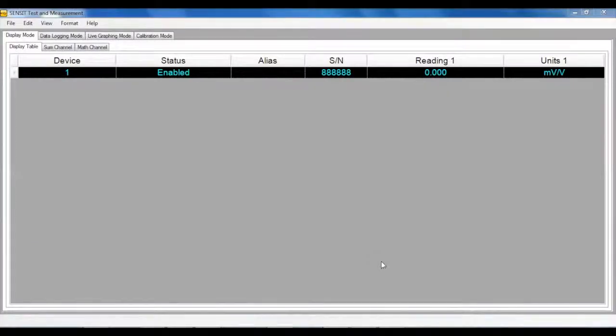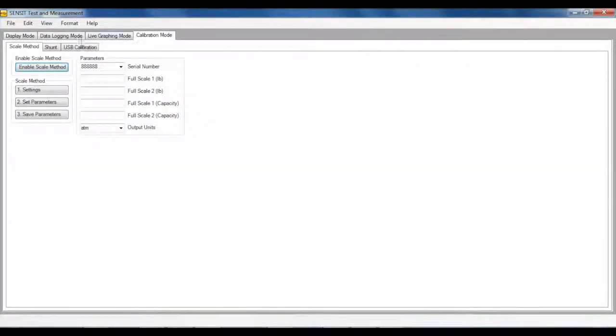In the SENSIT software, you can access the Scale Method on the Calibration tab below Scale Method. Click the Settings button to configure the Scale Method properties. Select the appropriate serial number stored in the USB device to be used under the Serial Number menu drop-down box. Next, fill in the remaining parameters.